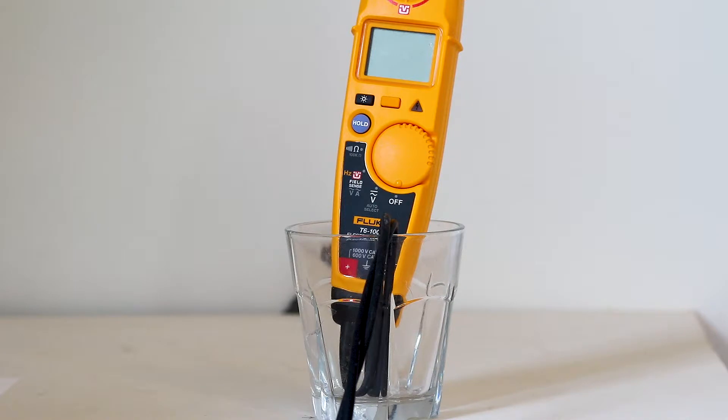The Fluke T6-1000 electrical tester resembles a clamp-on ammeter. Both are non-contact instruments, but rather than sensing a magnetic field, the T6-1000 senses voltage or current by means of capacitive coupling to ground.